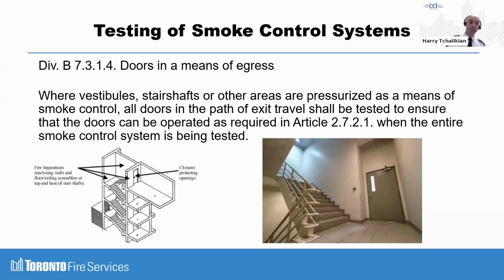We've always encountered issues with this, not on a mass scale, but this has come up once in a while for a very long time now, particularly in places like office buildings, where you have a giant pressurization fan at the top of the building, and it turns on to keep smoke out of the shaft in a fire alarm. That's what it's supposed to do. As a side effect of that, you pressurize this entire stairwell, and now this door won't open.